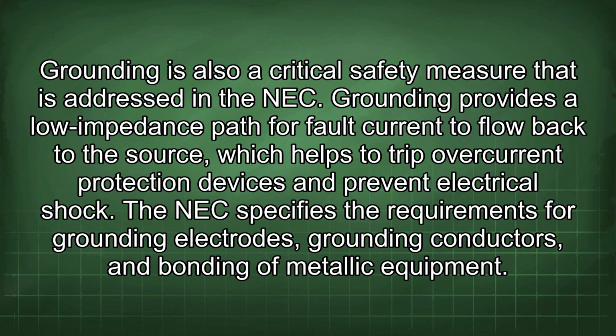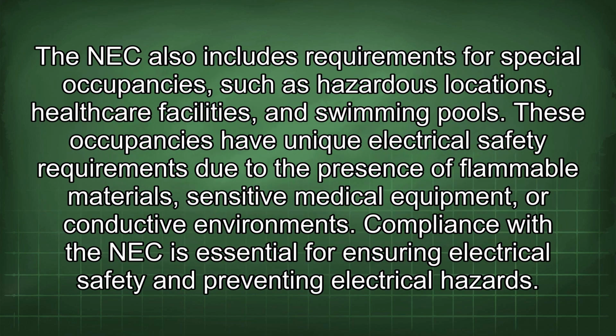Grounding provides a low impedance path for fault current to flow back to the source, which helps to trip overcurrent protection devices and prevent electrical shock. The NEC specifies the requirements for grounding electrodes, grounding conductors, and bonding of metallic equipment. The NEC also includes requirements for special occupancies such as hazardous locations, healthcare facilities, and swimming pools. These occupancies have unique electrical safety requirements due to the presence of flammable materials, sensitive medical equipment, or conductive environments.